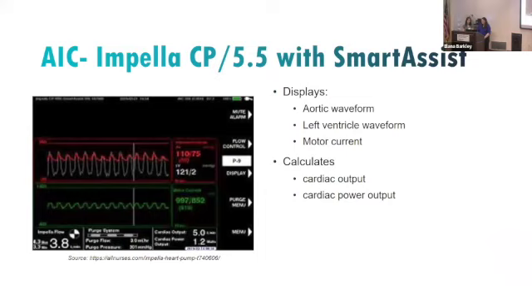Here's an image of the automated Impella controller for the Impella CP and 5.5. The red line here is the aortic waveform. The white line is the left ventricle pressure, and the green is your motor current. And on the bottom of the screen, it shows your Impella flow, current, purge flow, purge pressure, cardiac output, and cardiac power output. And then with the Smart Assist, it calculates the cardiac output and cardiac power output to aid in measuring end organ perfusion.